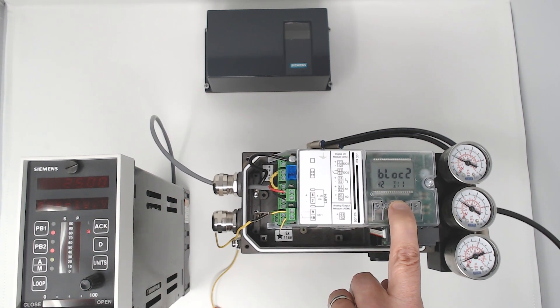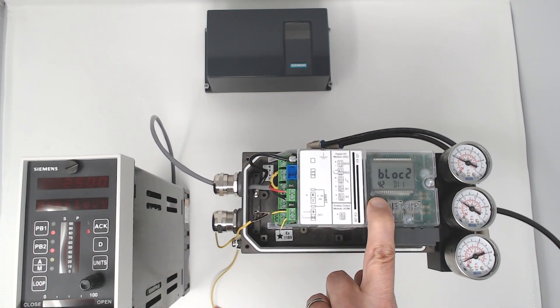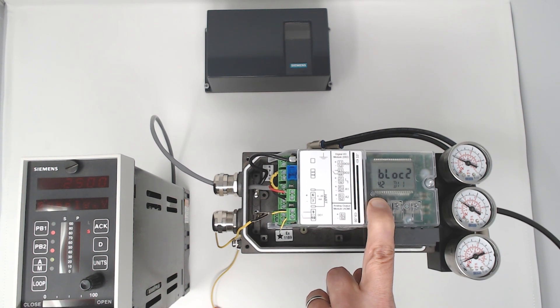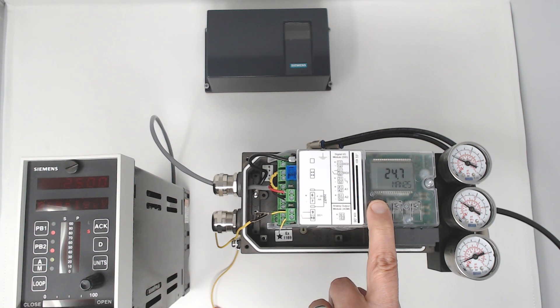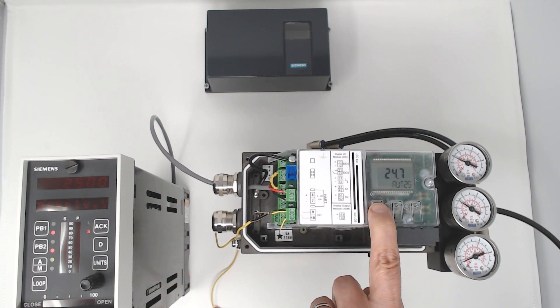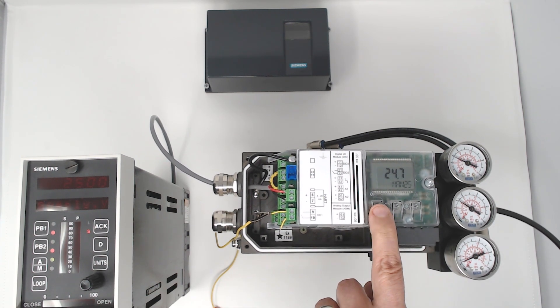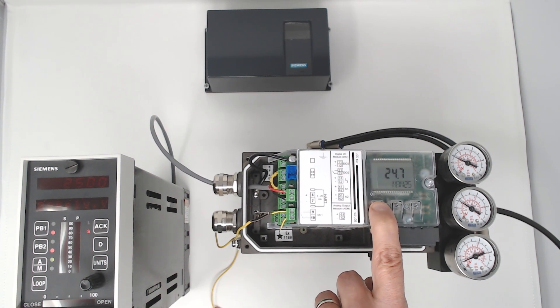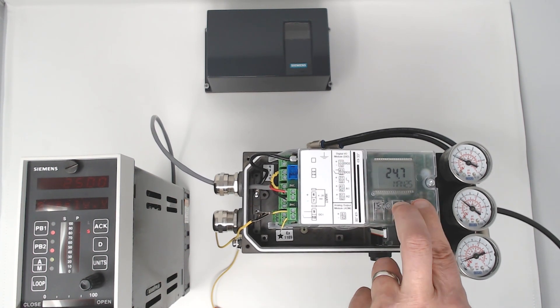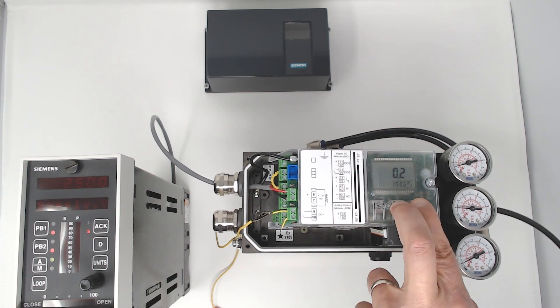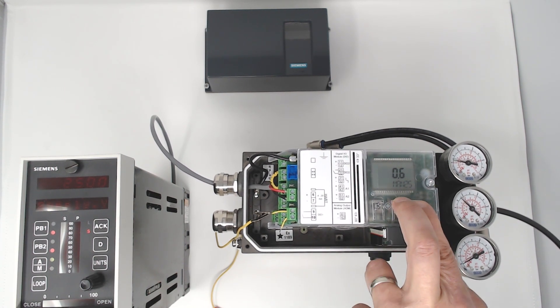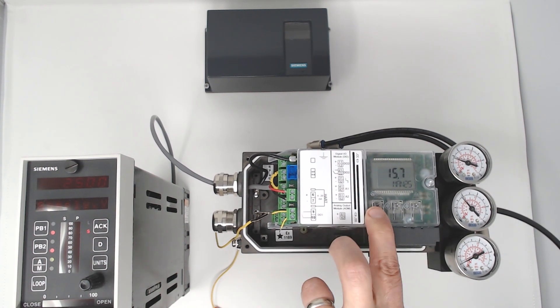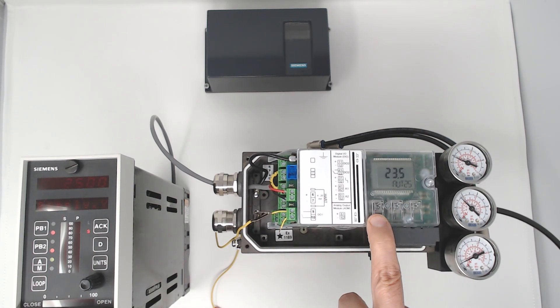Let's go back to block 2, which will prevent us from putting the positioner into manual mode and gaining access to configuration. As you can see, I can go in and out of manual mode, and in manual mode I can drive the valve anywhere I want with the local push buttons. Here's automatic control.